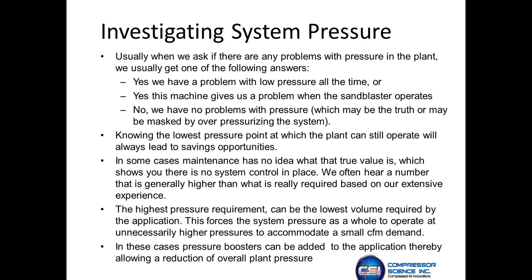But if someone knows that you're dialing the pressure down out in the facility, the first thing they're going to point to if there is a problem is the fact that you've dialed the pressure down, so dial the pressure back up. So it really has to be something that everybody buys into as far as lowering the plant pressure, so that you're actually monitoring the process to make sure there's no issue with the process while you're dialing the pressure down.